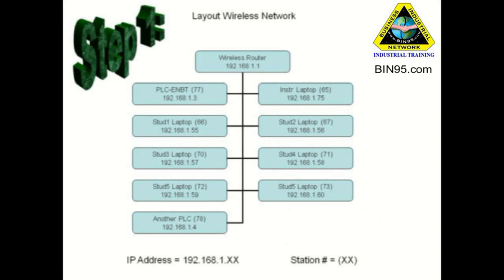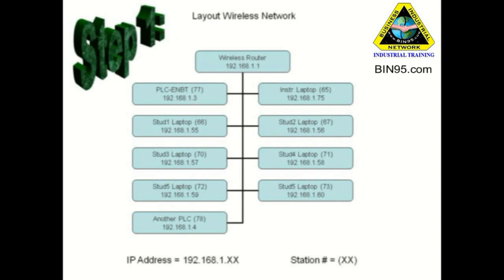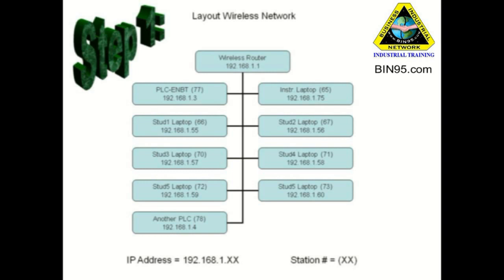Please pause the video at this point and look for a station number that's incorrectly addressed. Great! If you chose the device labeled 'another PLC,' which had a node address of 78 — a non-octal node address of 78 — then you chose correctly. The other numbers on each of the devices is the IP address. This is for the Ethernet network, so two different networks can access these devices that we've mapped out here. In summary, octal station numbers are just for the RSLinx Data Highway Plus network, and the decimal long IP address numbers are for Ethernet, which can also be the Ethernet driver in RSLinx.